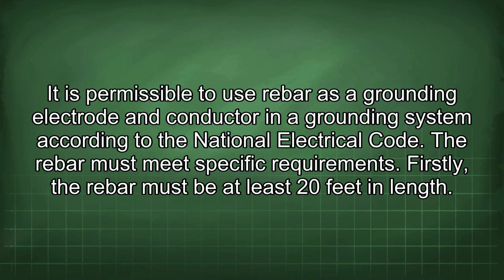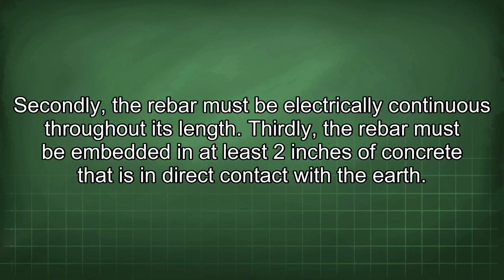It is permissible to use rebar as a grounding electrode and conductor in a grounding system according to the National Electrical Code. The rebar must meet specific requirements. Firstly, the rebar must be at least 20 feet in length. Secondly, the rebar must be electrically continuous throughout its length. Thirdly, the rebar must be embedded in at least 2 inches of concrete that is in direct contact with the earth.